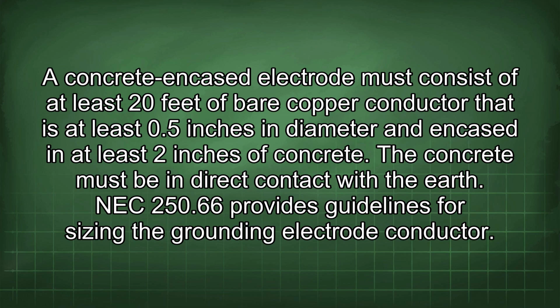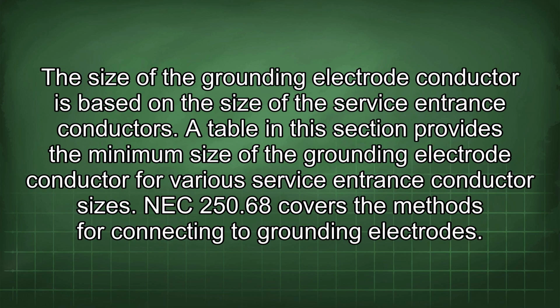NEC 250.66 provides guidelines for sizing the grounding electrode conductor. The size of the grounding electrode conductor is based on the size of the service entrance conductors. A table in this section provides the minimum size of the grounding electrode conductor for various service entrance conductor sizes.